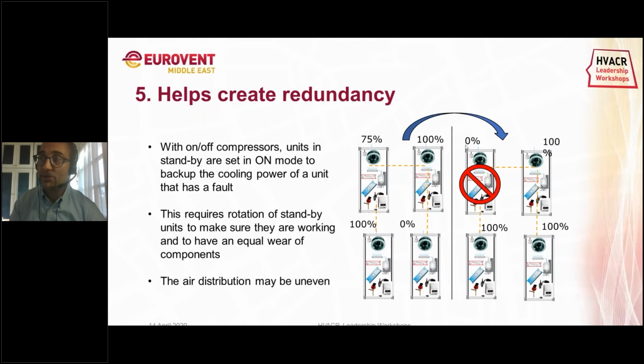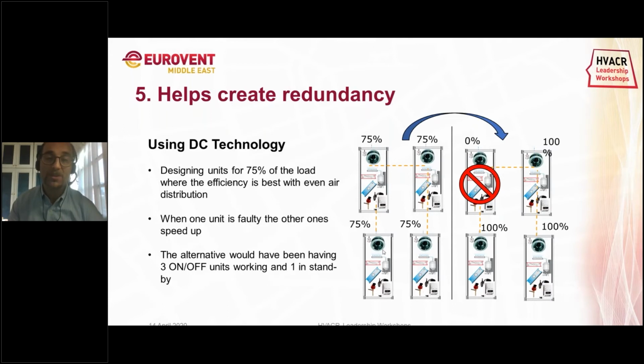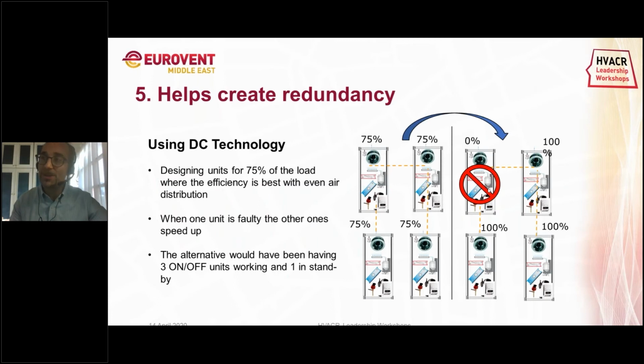Whereas if you have modulating units, you could design the system to have all the units, or more units, operating at partial load. At partial load, one of the characteristics of these compressors is that they are very, very efficient. So it's better to run them at partial load, with all the units running. This will result in a better air distribution, because you have 4 units, imagine they are in the corner, and only when one unit has a problem, all the others can accelerate to obtain 100% and have a backup of the cooling power needed. All right. So these are reasons why this technology is becoming really popular for data center cooling for DX systems.